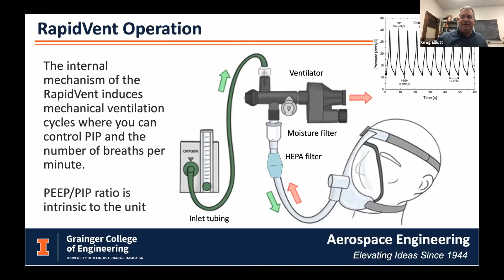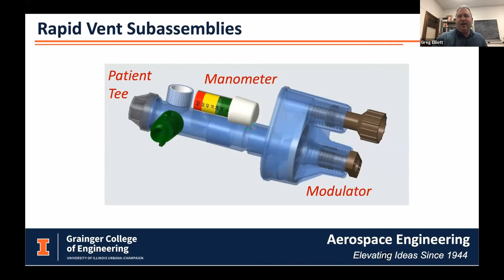The PEEP and PIP ratio is an important ratio. In other words, the highest pressure to the lowest pressure is an important ratio that they want to be able to set. And so we would show that we could change the breathing rate and set that ratio as they were accustomed to with the more electronic ventilators they would have in the hospital. This is the RapidVent. This is a CAD drawing of it. I'll go over quickly the parts of this ventilator. It basically had three sub-assemblies: the patient tee, a manometer, and a modulator.